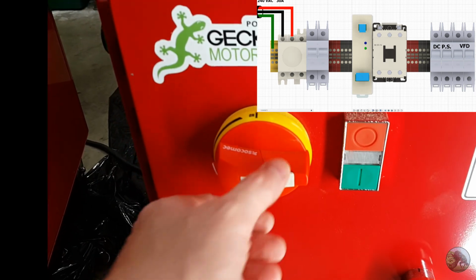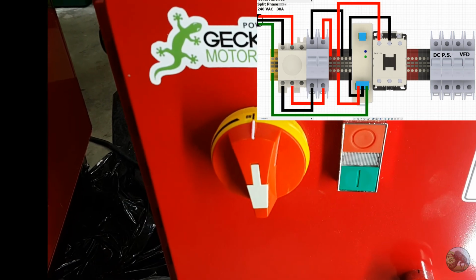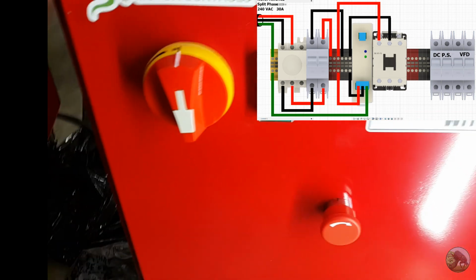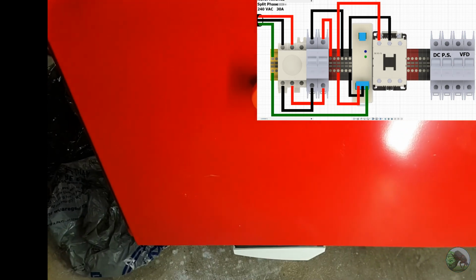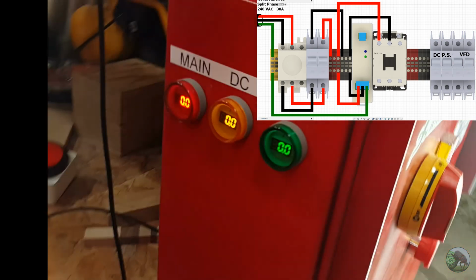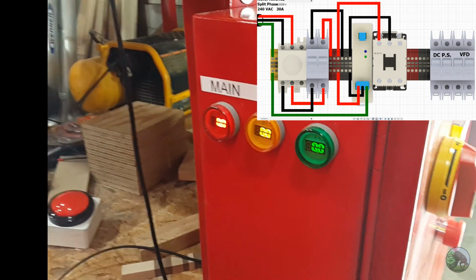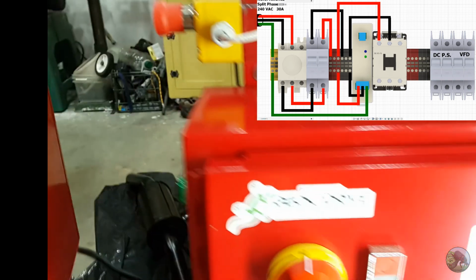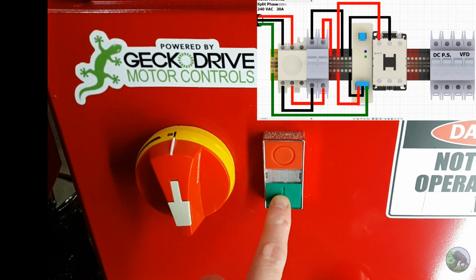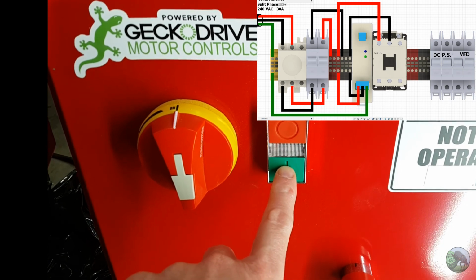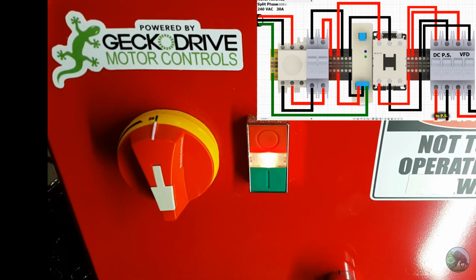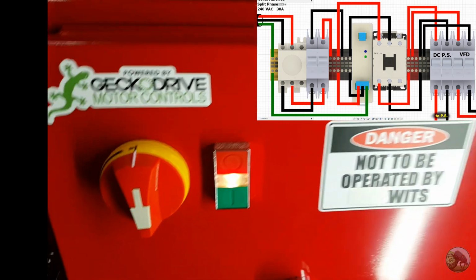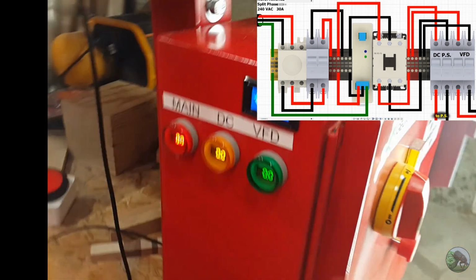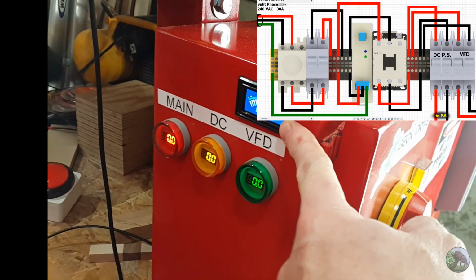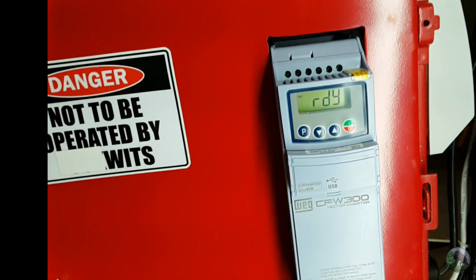So here at the machine, the first thing we do is we turn on the rotary disconnect, and we hear the Stego fans coming on. We also see the ammeters come alive. And then we hit the actual switch, which is part of the latching circuit, turns on the contactor, and that powers the rest of the machine. So here we have an indicator. That's the temperature sensor for my Gecko drives, and the VFD is now online.